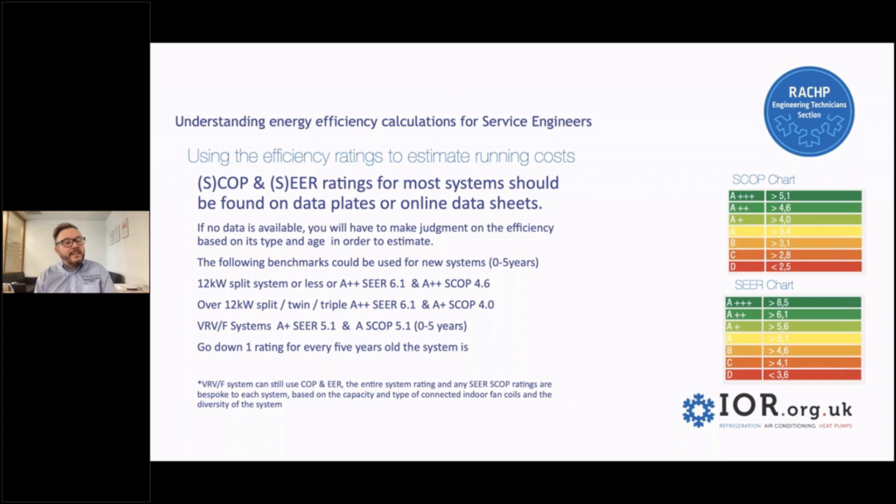If I were looking at a system that's over 12 kilowatt — it might be a split, a twin, or a triple — then I'd probably be looking at calculating using A++ and A+, so I'd have a SEER rating of 6.1 again, and a SCOP rating of 4.0.